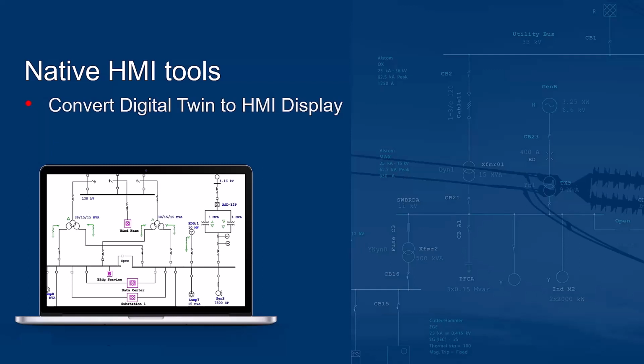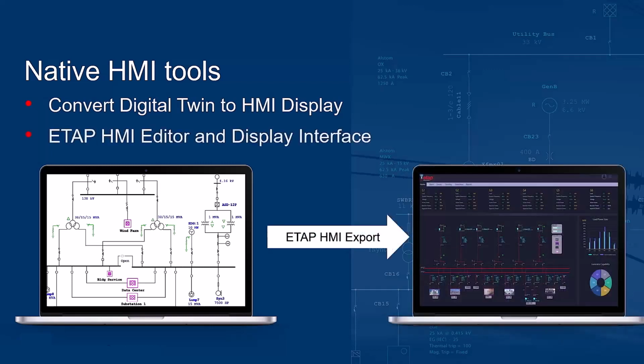From ETAP, you can export your model and quickly create HMI tools. This helps reduce the time invested in animations required to display the correct color for energization. By using the ETAP model, the ETAP HMI engine uses the same switching device continuity coloring just like ETAP. Therefore, if an element is energized in ETAP, it will also show energized in the ETAP HMI.